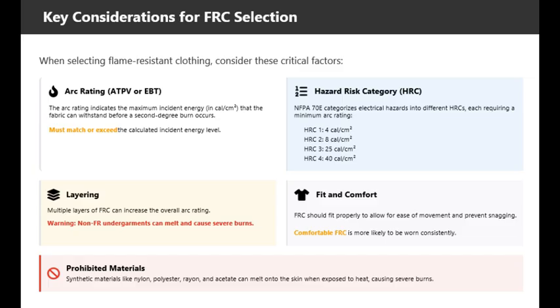Finally, there are prohibited materials you must avoid. Synthetic materials like nylon, polyester, rayon, and acetate can melt onto the skin when exposed to heat, causing severe burns. These materials should never be worn as outer layers or undergarments when arc flash hazards are present.